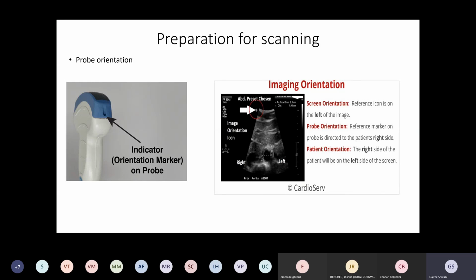Then you'll need to check the orientation of the probe. So all ultrasound probes will have an orientation marker. It might look a little bit different depending on the type of probe that you're using. And that corresponds to the orientation marker on the scan on the screen. So you can see in this example, the orientation marker is on the left-hand side of the screen. And you can change it actually, but normally it's on the left-hand side. And that means that when you're scanning somebody, whatever is closest to the orientation marker on the probe will show up on the left-hand side of the screen. And that's really important, especially when you're trying to work out fetal position with scanning.